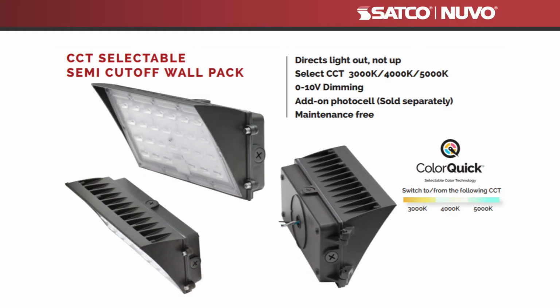Color selectability, or color quick, has also come to exterior fixtures. Our semi-cutoff wall pack directs light out but not up. The selectability in color temperature is 3000, 4000, and 5000. The fixture is 0 to 10 volt dimmable, and photocells are available.